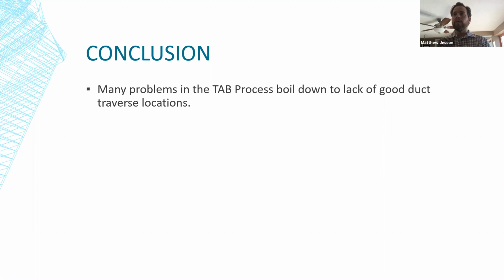If you don't have room for a good duct traverse, then you're also not getting fully developed flow, and you're increasing your pressure drop in the system. We are, of course, brilliant geniuses, but we're not magicians, unfortunately.